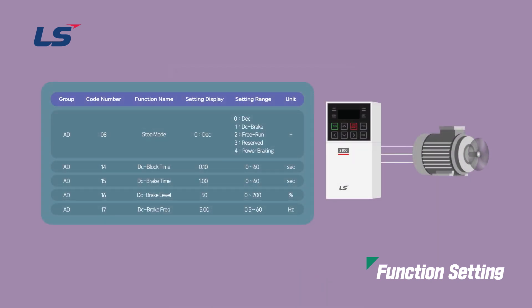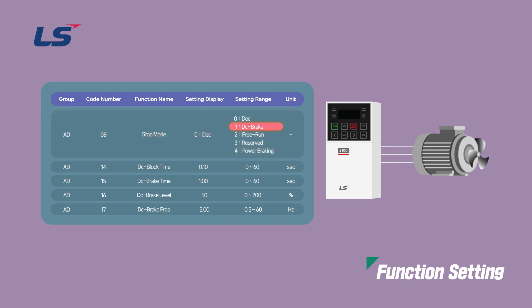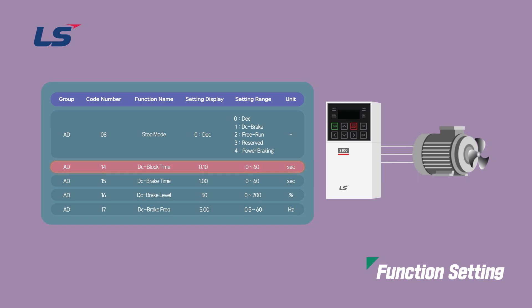The DC brake stop method is used for high speed spindle motors, which can move slightly due to high speed inertia even after stopping, to apply direct current braking to bring the motor to a complete stop. Select 1 DC brake in stop mode at AD8. The frequency set in AD17 DC brake frequency will apply DC voltage to the motor and stop it when it reaches that frequency level during deceleration. AD14 DC block time sets the time to block the AC drive output before starting DC braking. AD15 DC brake time sets the time to apply DC voltage to the motor. AD16 DC brake level sets the amount of DC braking based on the motor's current rating.